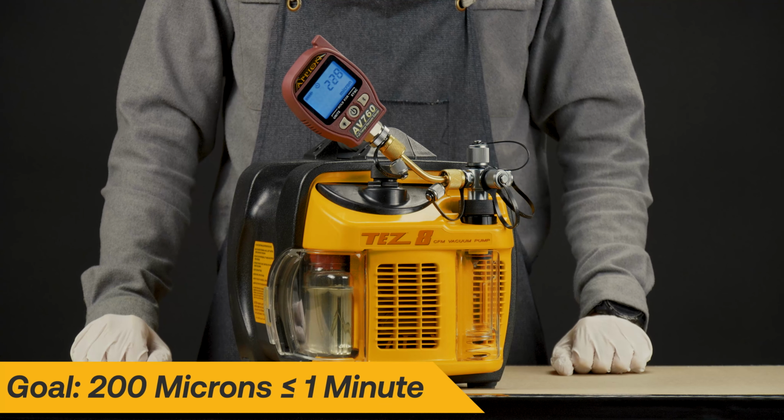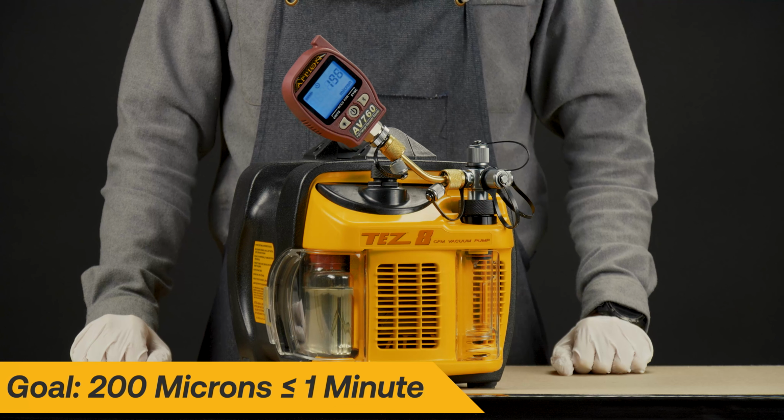If you've successfully reached 200 microns in a minute or less, then the test is deemed successful.